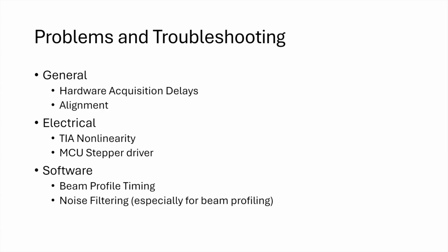For software, we've been having some problems with the beam profile timing. We have figured out that the data that we want is streaming too late in the timing, and that is causing delays for our next scan acquisition, which was causing problems with our data collection and the correctness of it. We figured out that we can do a first scan and that is perfect. So we skip to just repeating that first scan and taking out the repeated scans after that.